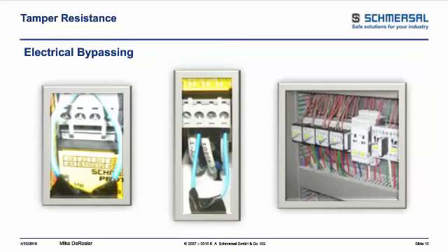And in both those pictures, with that jumper wire, you can see it's marked with electrical tape for that sole purpose. It's not numbered, it's not part of the original design, but those terminals are S11, S12, and S21 and S22, which are the redundant safety inputs.